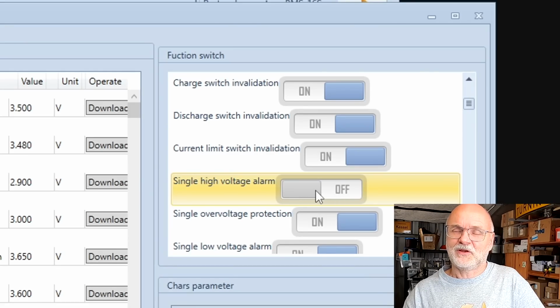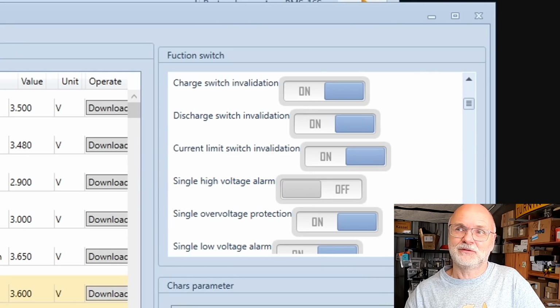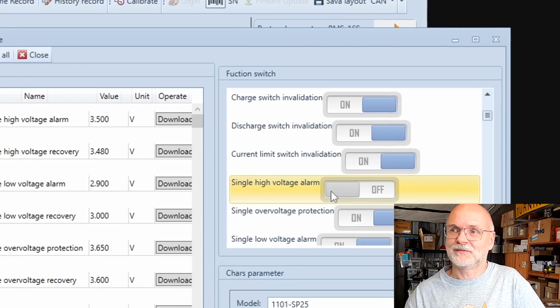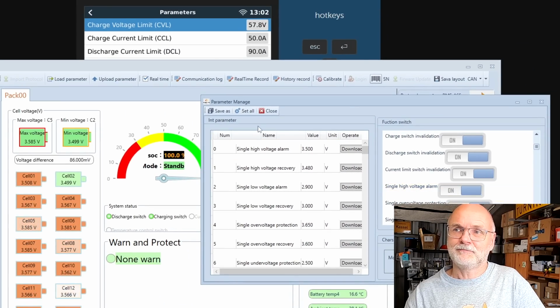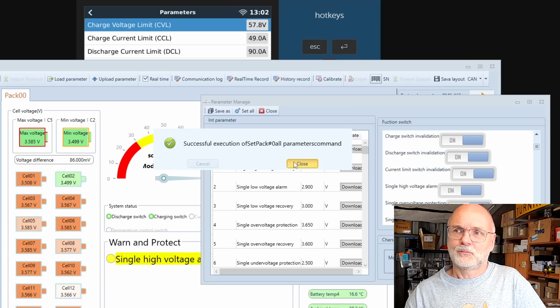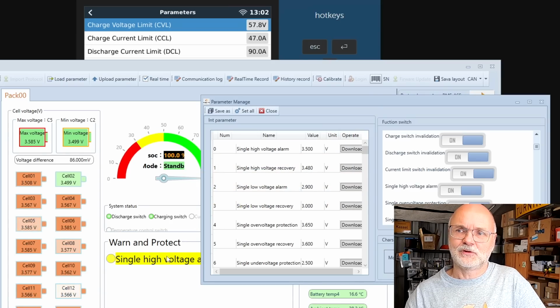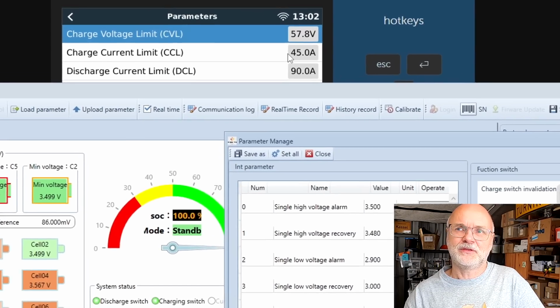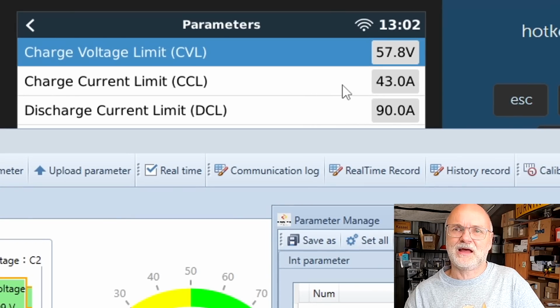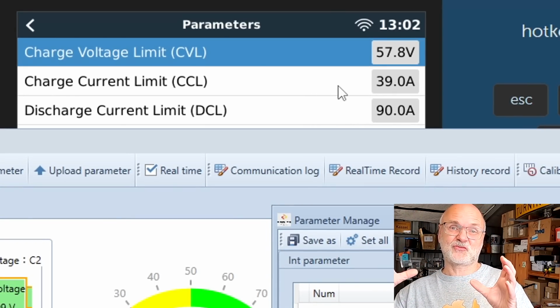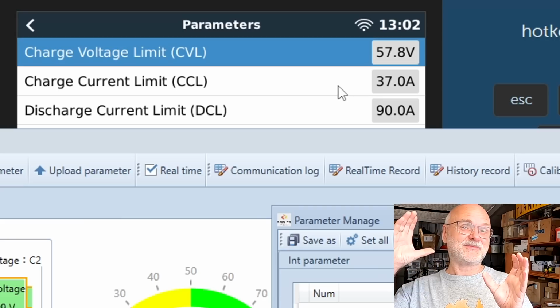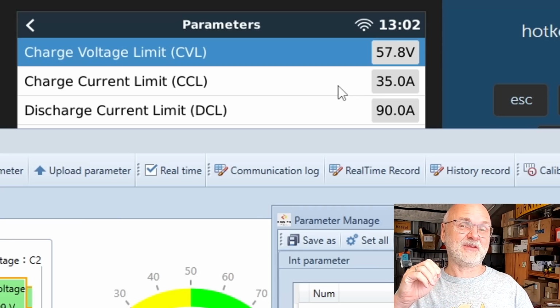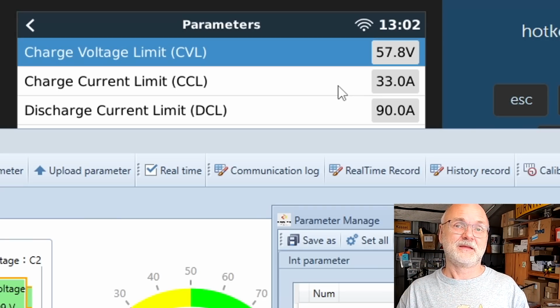When I turn this one on, we will get an alarm and the charge current goes to 10 amps. Look at this, I turn this feature on, go to set all, and we will get an alarm straight away, single high voltage alarm, and you can see how the charge current limit goes down to 10 amps now. This would limit my charge controller to 10 amps output, regardless if into the battery or to load.